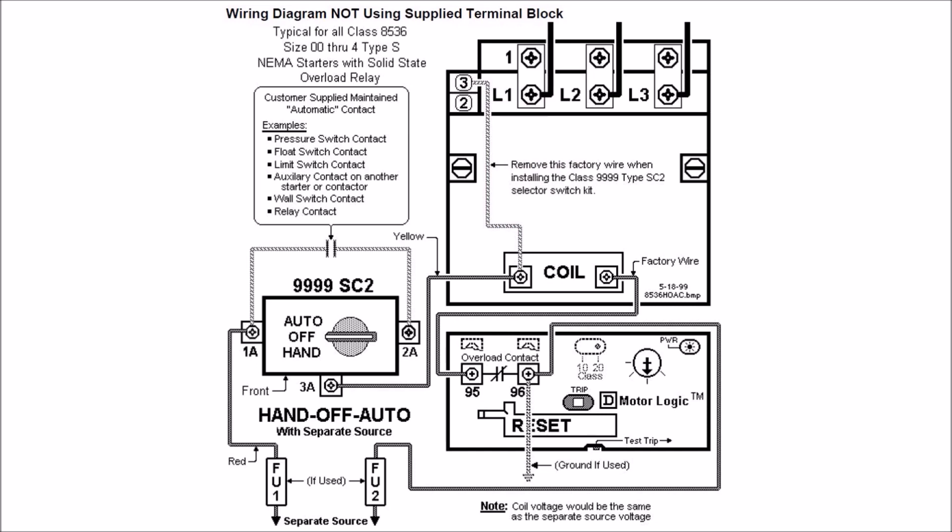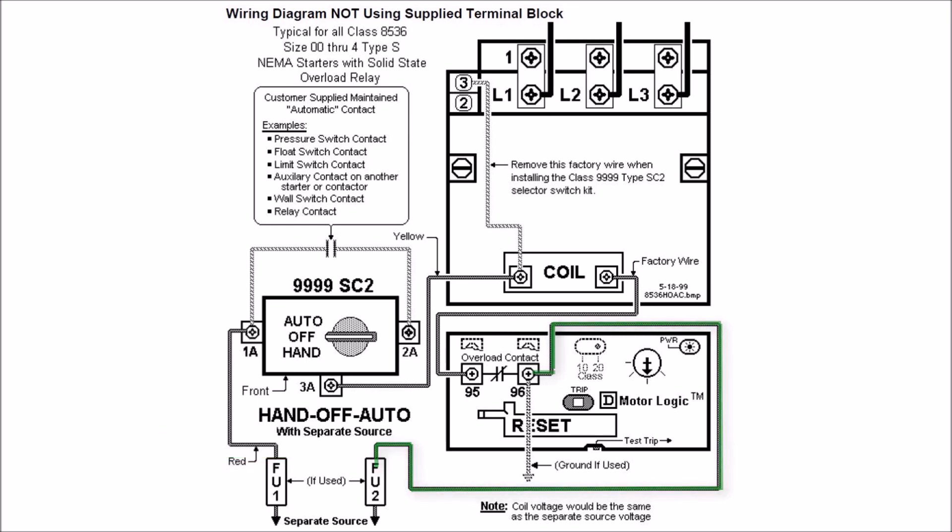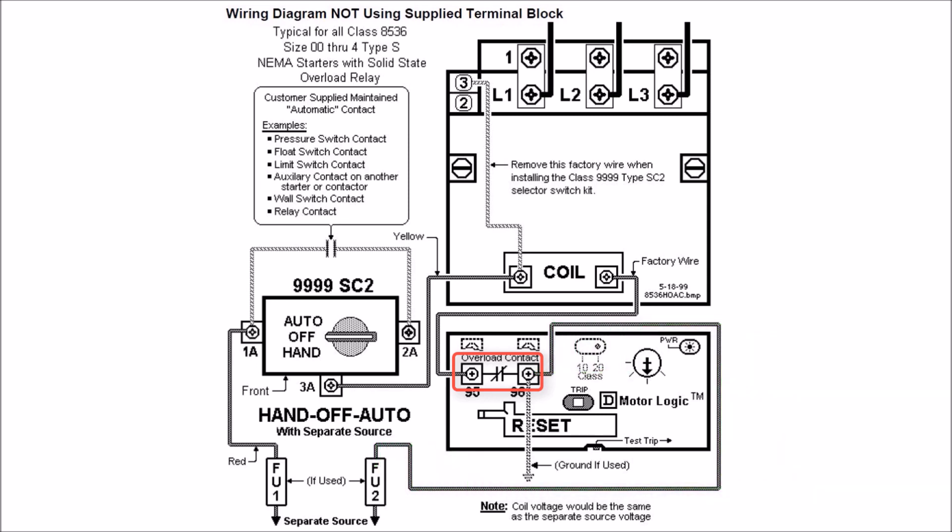For wiring here, you'll actually have your one leg of your separate control source, usually your neutral in your 24 volt, 120, and 277. If you have 460 or 480 three phase, it's just your other secondary wire. You're going to wire from there to the right-hand side of your overload relay, which is going to have a normally closed contact here that indicates trip and breaks that circuit.